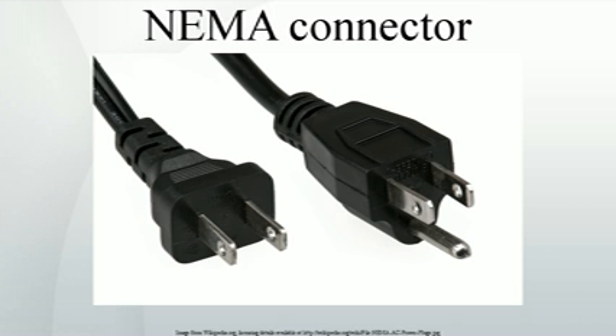Generally 6 series non-locking plugs are used for such appliances as large room air conditioners, commercial kitchen equipment, and the occasional home arc welder. Single-phase 6-50 is commonly used on farms for the silo unloader, and is used with a 6-gauge flexible power cord up to 200 feet long, 61 meters.